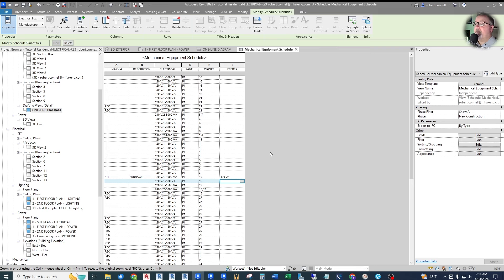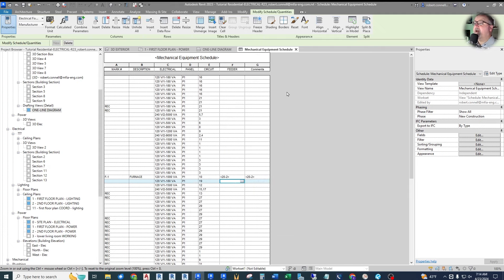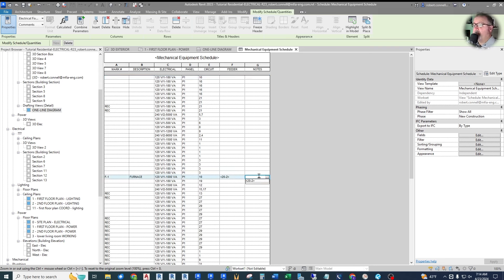Some people come in and type the actual half-inch conduit with two number-12 conductors, etc., but we don't do it that way — we find it can be error-prone, so we use this feeder tag method. The final column I like to include is a Comments column, for when you need to say something special about equipment — for example, sometimes an indoor fan coil unit is powered from the outdoor unit. We can add a built-in field called 'Comments' for that, which can also serve as notes.